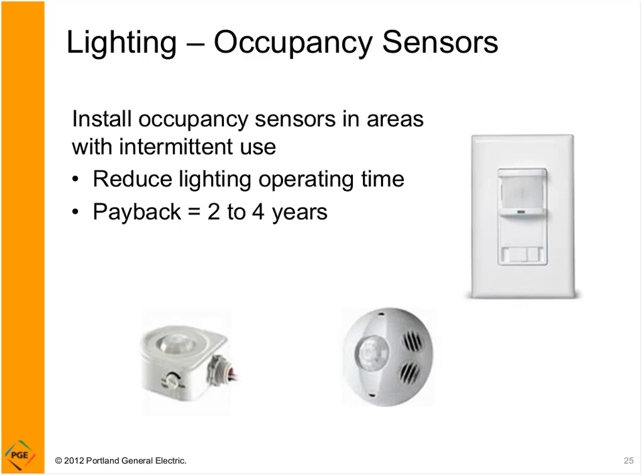We have a few different types of occupancy sensors here. On the far left is a fixture-mounted occupancy sensor. When we were looking at the high bay fixtures, you might see something like this on a high bay fixture. Moving to the right, in the middle, the round sensor is ceiling mounted and maybe needed for some installations. And then on the far right, this is just a switch replacement, wall-mounted occupancy sensor. It's really common to see these types of sensors in a meeting room or individual offices.